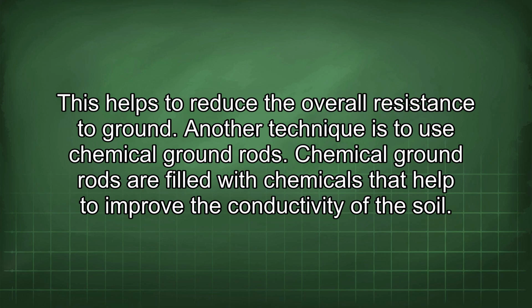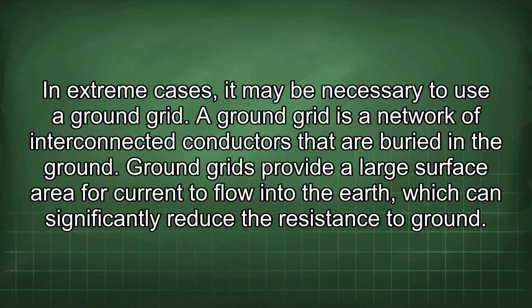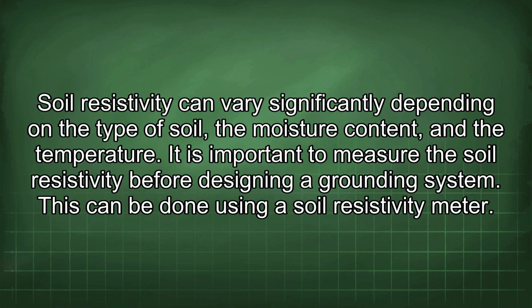Another technique is to use chemical ground rods. Chemical ground rods are filled with chemicals that help to improve the conductivity of the soil. In extreme cases, it may be necessary to use a ground grid. A ground grid is a network of interconnected conductors that are buried in the ground. Ground grids provide a large surface area for current to flow into the earth, which can significantly reduce the resistance to ground. Soil resistivity can vary significantly depending on the type of soil, the moisture content, and the temperature.